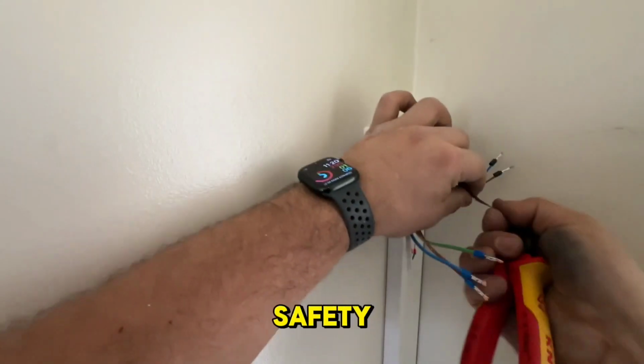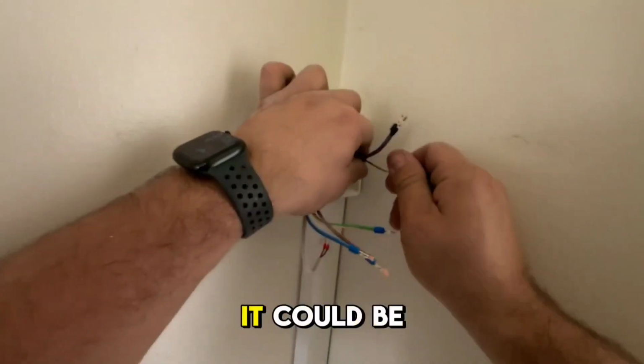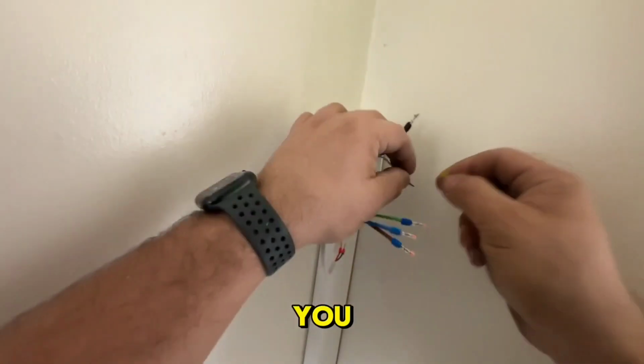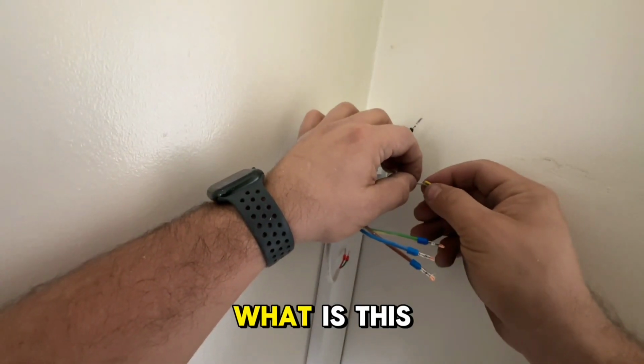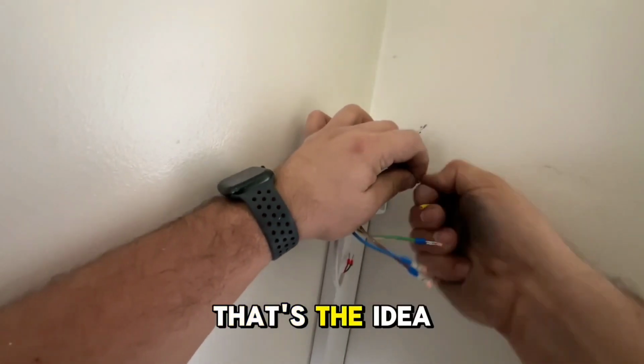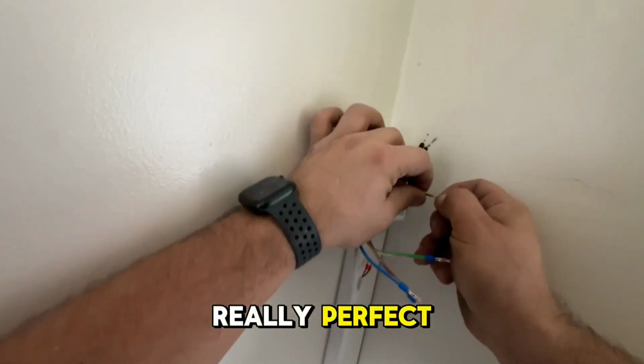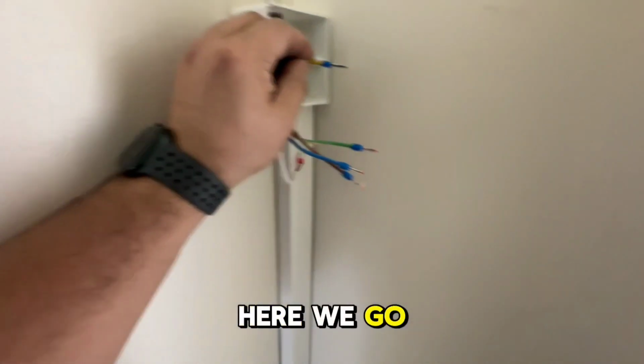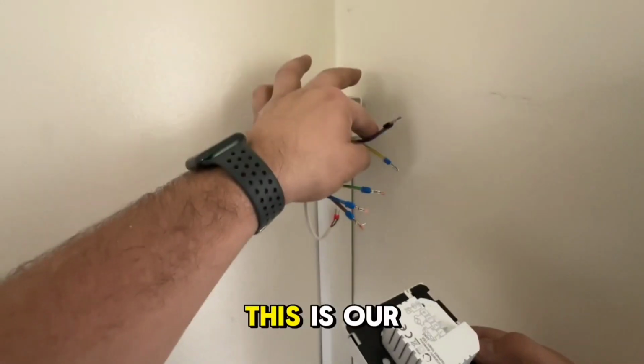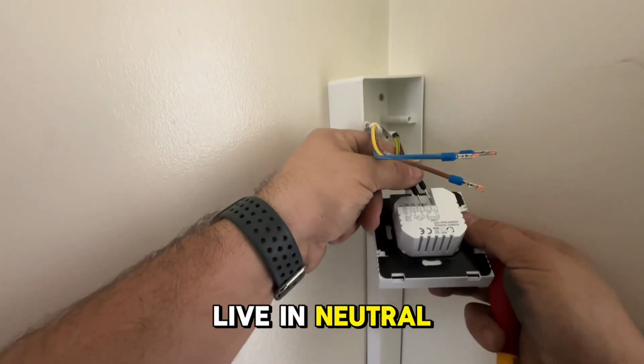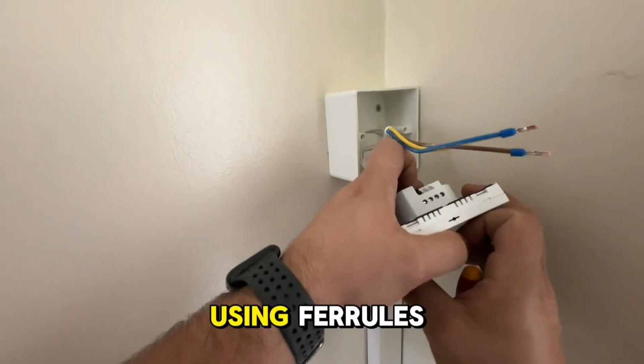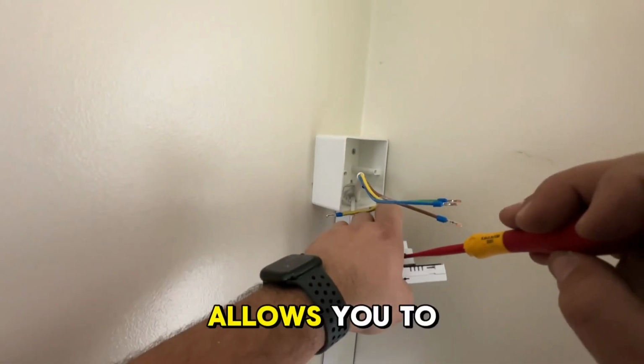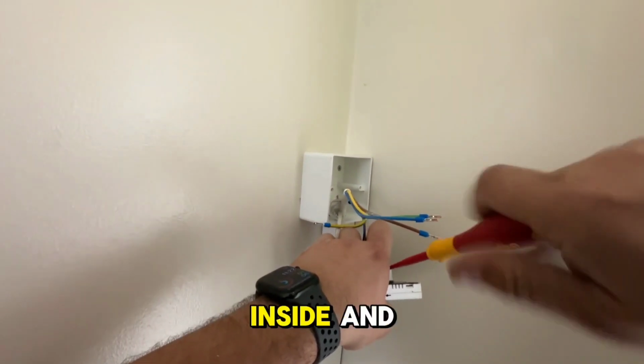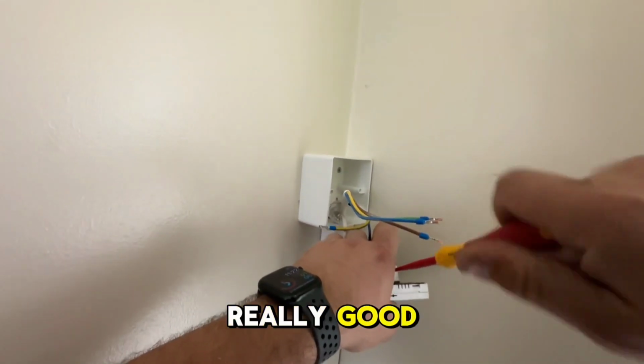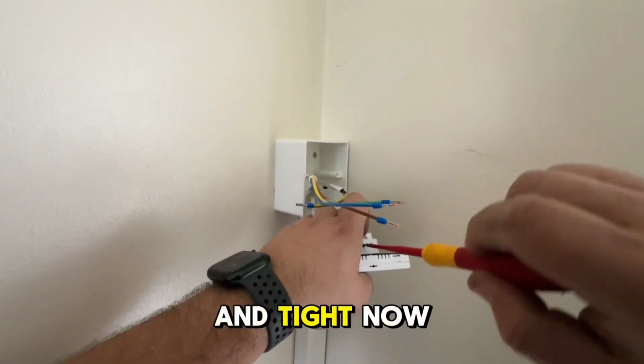That's for client's safety. It could be a tape, it could be anything actually, as long as you identify what is this, and that's the idea really. Perfect. Here we go. Lovely. Back of a thermostat. This is our load, and we've got live and neutral. And using ferrules as well allows you to really push that cable inside and making sure you've got really good contact. Make sure it's nice and tight.